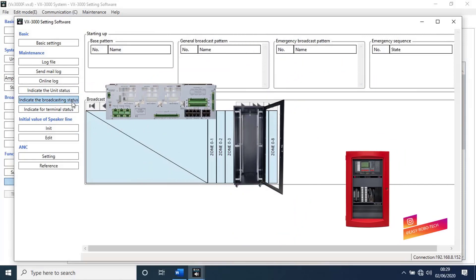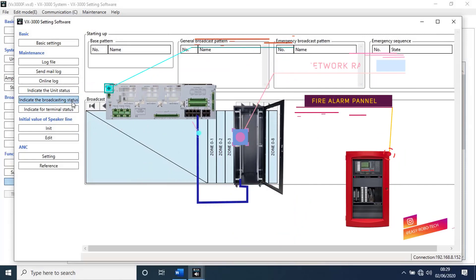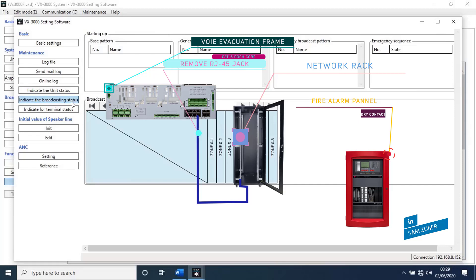Take a CAT6 patch cord. One end connect to unit and other end of the cable, remove RJ45 jack. Then slice orange pair and touch to rack earthing. It will start broadcasting emergency sequence.